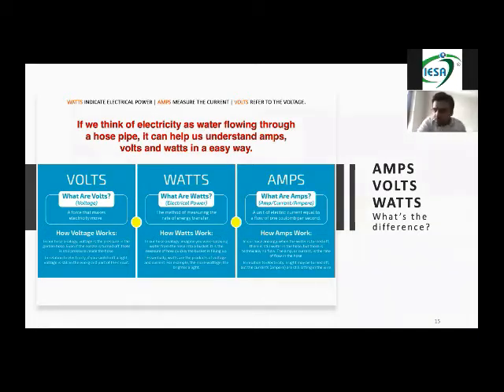That is the calculation. And if you want to convert kilowatts to amps, 1 kilowatt in a three-phase system, you can multiply by 1.7. So that is your amps. This is the basic calculation, what you have to remember always.